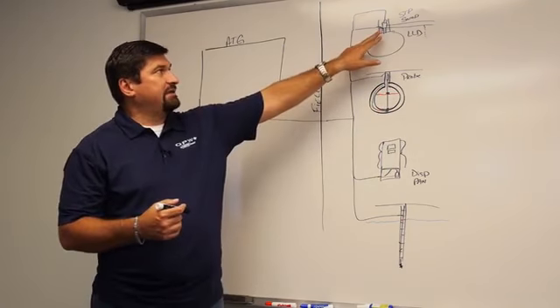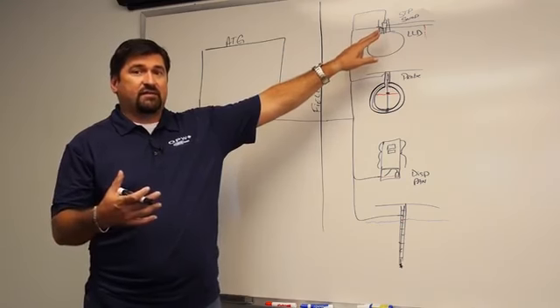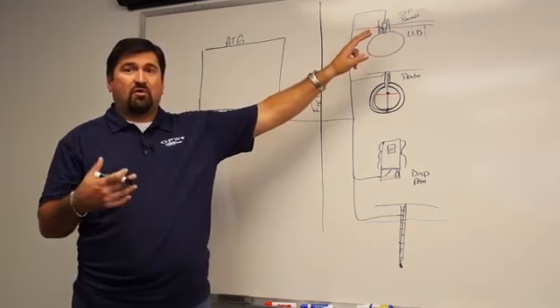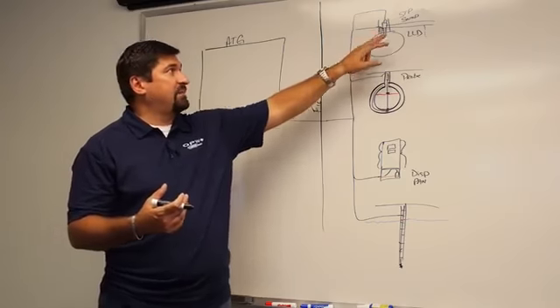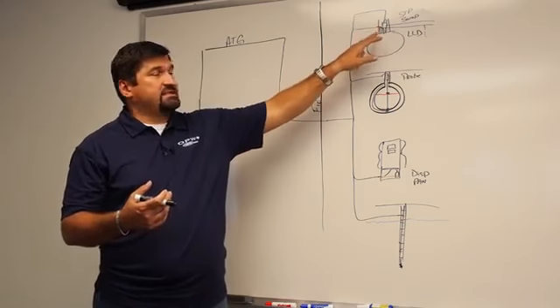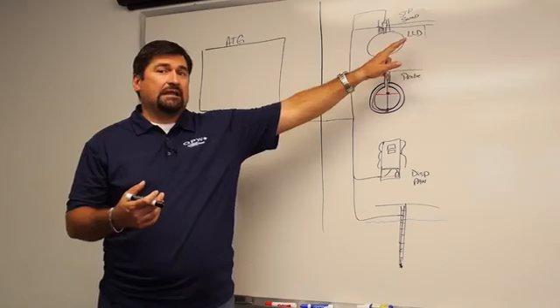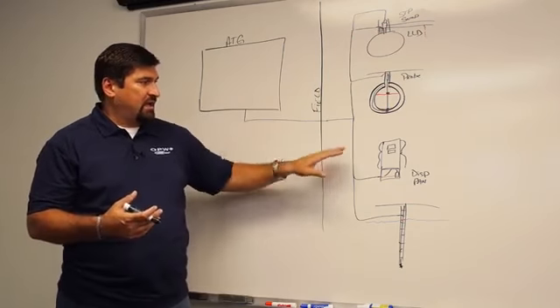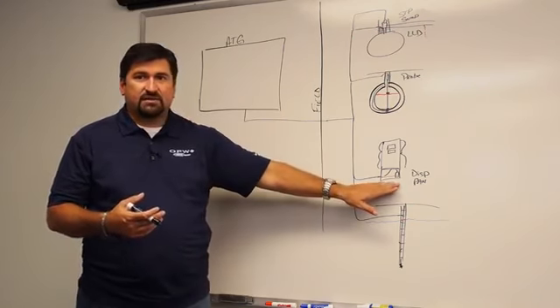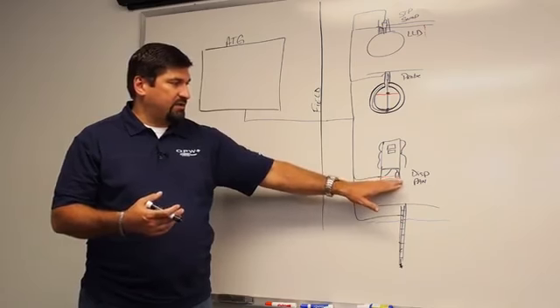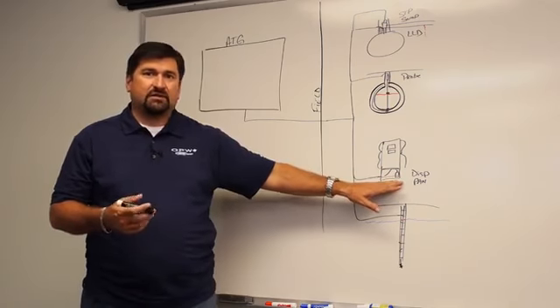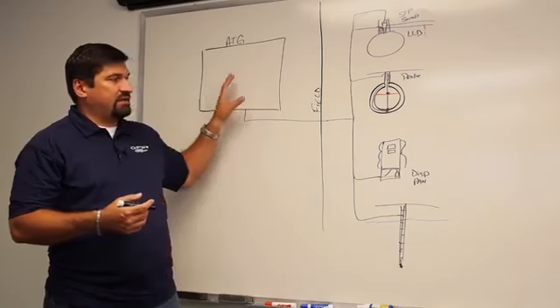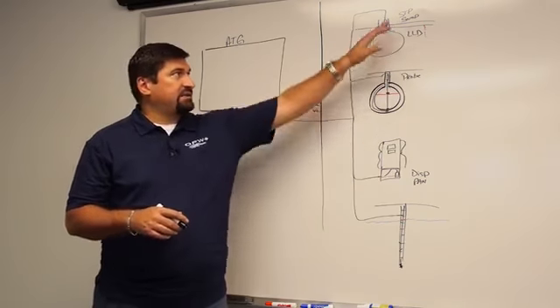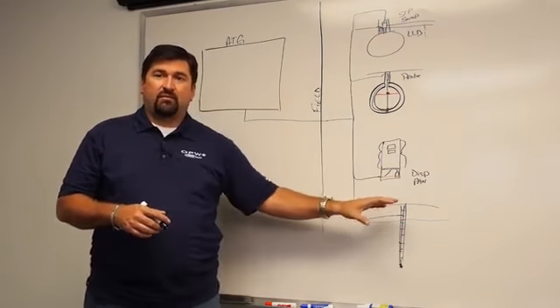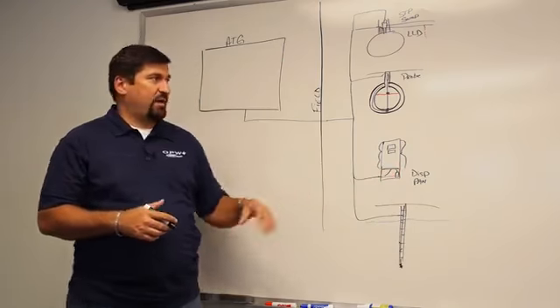It's constantly looking at the STP sump to know if there's any type of fluid that may be coming from the motor or from the secondary containment of the pipe. It also could be controlling the STP motor if you're running some type of electronic line leak system. It's also monitoring underneath the dispenser pans, so that if I get collection underneath the dispenser pan, that console can turn off a relay to shut down the motor to prevent product from going back into these dispenser pans.